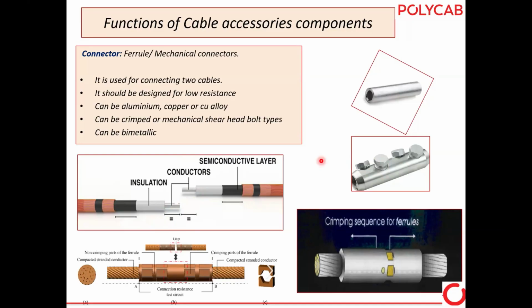First thing, its design is for low resistance. Its resistance should be low, as equal as the cables. Then it might be aluminum, copper, or copper alloy, depending on the cables. If the cable is copper, we have to use copper ferrules. If it is aluminum, we can use aluminum ferrules.